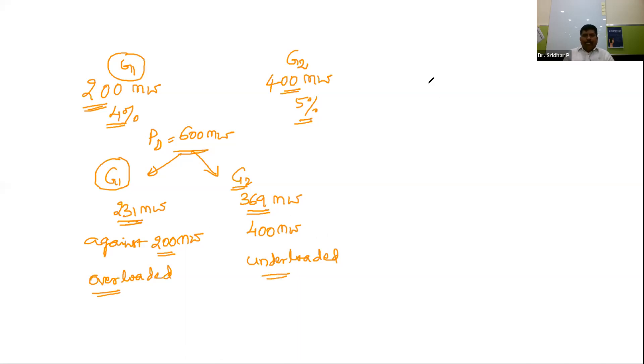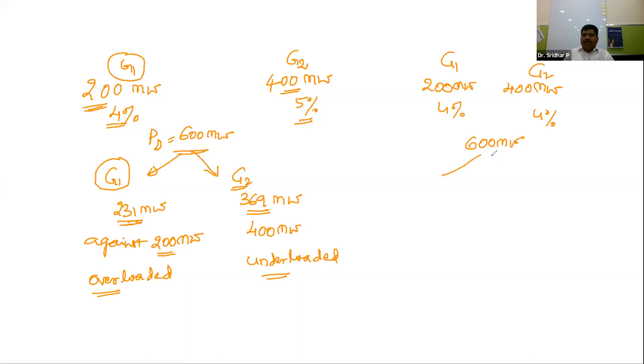If both generators had the same droop — say 4% — then the 600 MW load would be shared proportionally: G1 takes 200 MW and G2 takes 400 MW. This is the ideal distribution when droop characteristics are equal.